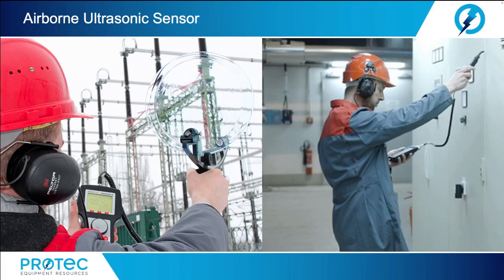Another type is the parabolic dish concentrator, which is used to extend the distance range of the ultrasonic microphone. The parabolic dish is ideal for checking bushings and insulators for surface tracking and harmful corona. When airborne ultrasonic signals are detected on exposed insulator surfaces, the parabolic dish enables very quick and precise pinpointing of the partial discharge location. Airborne ultrasonic is best for detecting corona and surface tracking. Floating electrode PD will also produce a weak airborne ultrasonic signal. When airborne ultrasonic signals are detected within enclosures, it is not immediately possible to determine the exact location of the partial discharge. By using multi-channel PD receivers, multiple ultrasonic contact sensors can be used to triangulate the signal origin.